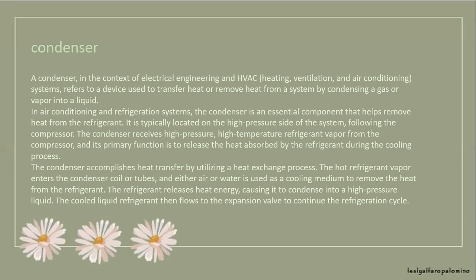The condenser accomplishes heat transfer by utilizing a heat exchange process. The hot refrigerant vapor enters the condenser coil or tube, and air or water is used as a cooling medium to remove heat from the refrigerant. The refrigerant releases heat energy, causing it to condense into a high-pressure liquid, which then flows through an expansion valve to continue the refrigerant cycle.